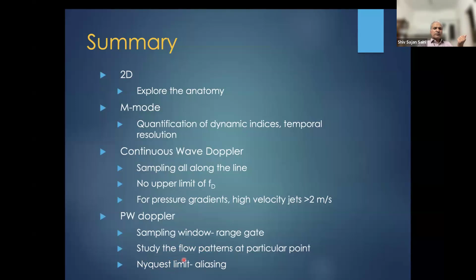Continuous wave Doppler is used for all regurgitant lesions, or any lesions where you need to pick up a very high blood flow velocity, more than 2 meters per second. Pulse wave Doppler is used to measure the velocity at a particular given point, but remember that the phenomenon of aliasing can happen if the frequency of the signal is more than half of the pulse repetition frequency. To improve that, you increase the pulse repetition frequency of the signal.